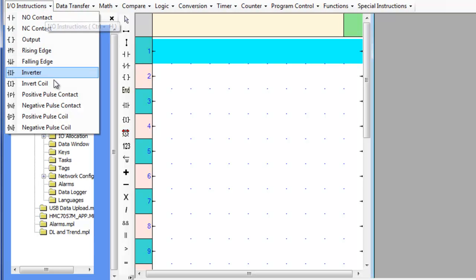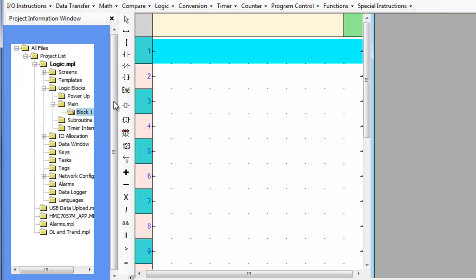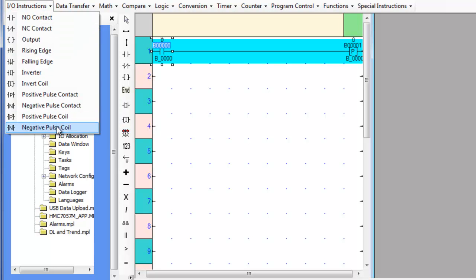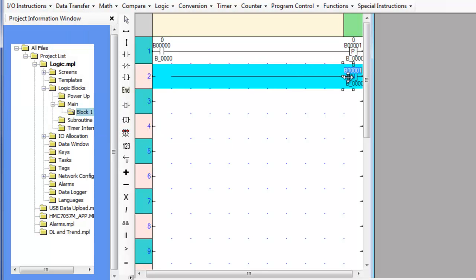The positive pulse coil is an instruction which will turn on the associated bit for one scan of the logic blocks when the preceding conditions become true. The negative pulse coil is an instruction which will turn on the associated bit for one scan of the logic blocks when the preceding conditions become false. The execution time for these instructions is 1.3 microseconds.